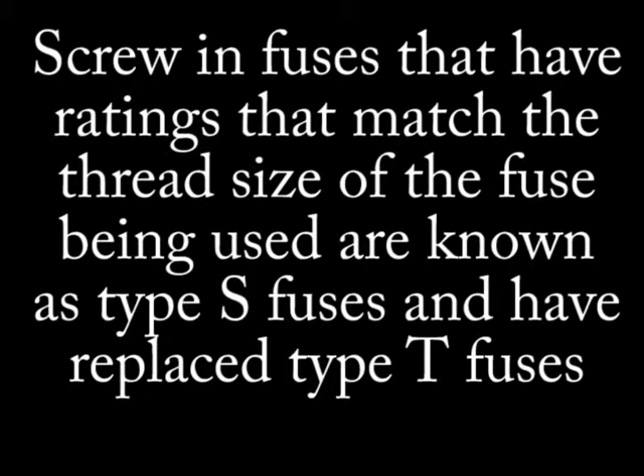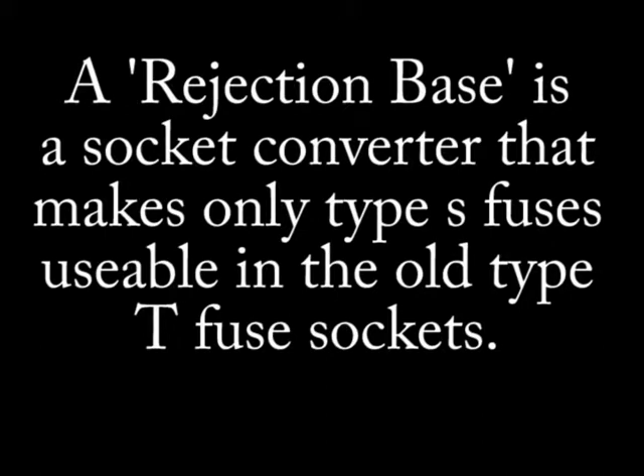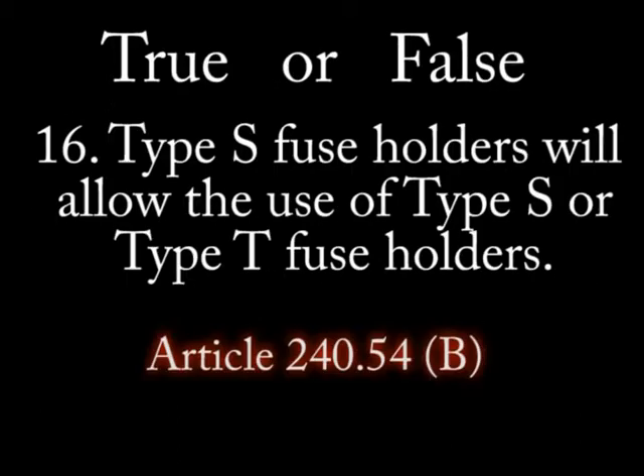This type of fuse was changed to screw-in fuses that had different thread patterns for each amperage. These are known as type S fuses. Type S fuses took the error or cheating factor out of the fuse replacement. One more item, and that is called a rejection base. It is a device that allows the usage of type S fuses in type T fuse panels. Let's proceed to question number 16.